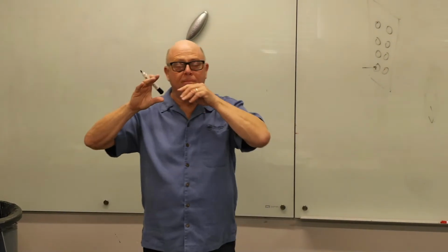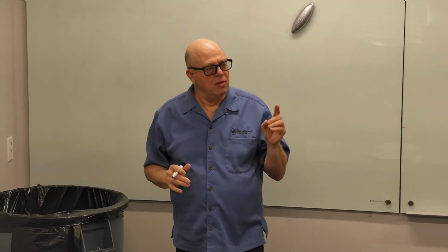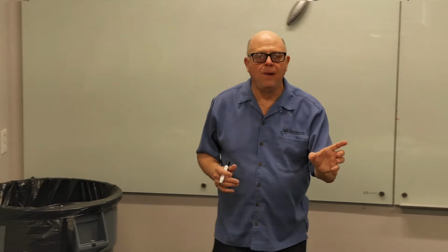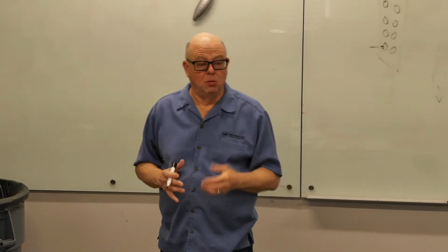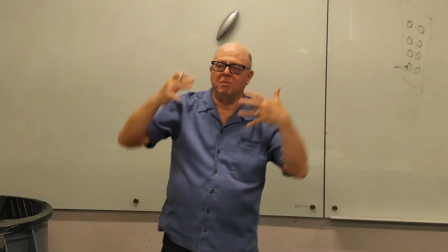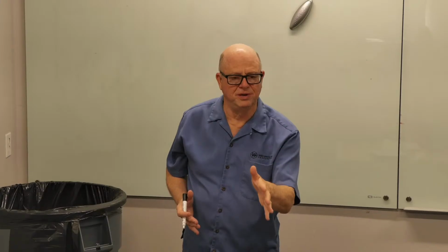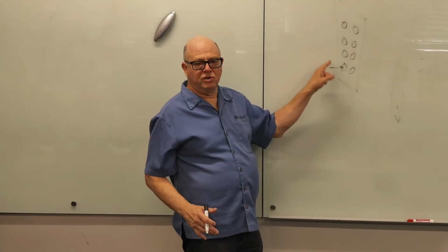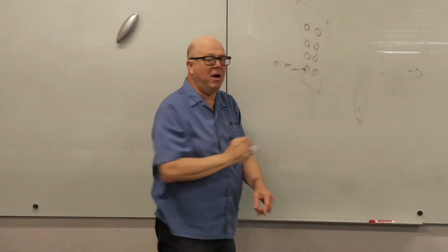But the wires aren't transmitting analog. The old gauges that we used to use, pressure gauge or an amp meter or something like that, those are all analog. The cell phones that we had up until 1991 or 2 were analog. And their signal was not as good because a digital signal is a more robust thing. It can overcome a lot of things that an analog signal has more difficulty doing, and digital is less expensive. So we went to digital signals. But ultimately, if you're going to watch a video or you're going to talk to somebody, your world is analog, right? So the question was, are we taking an analog or a digital signal into these ECM motors? So part of that is understanding what's an ECM motor.